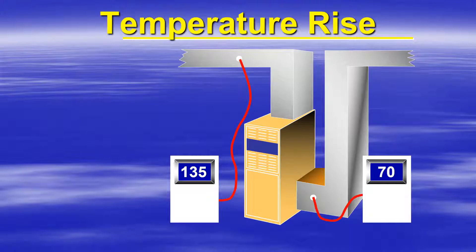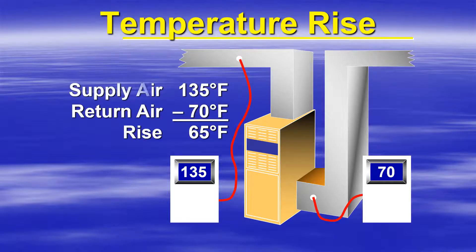Taking our return air temperature and our supply air temperature — in this example we have a 70-degree return air and a 135-degree discharge air. We take these two numbers and subtract them to get our temperature rise of 65 degrees. We then go back to our furnace data chart and find our air temperature rise parameters.